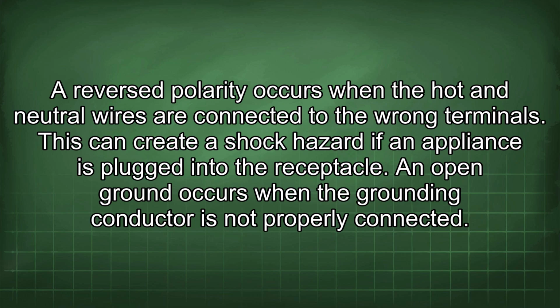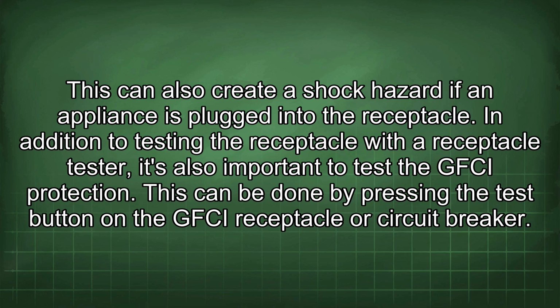A reverse polarity occurs when the hot and neutral wires are connected to the wrong terminals. This can create a shock hazard if an appliance is plugged into the receptacle. An open ground occurs when the grounding conductor is not properly connected. This can also create a shock hazard if an appliance is plugged into the receptacle.